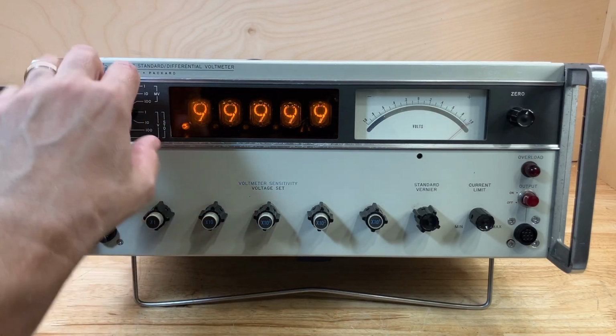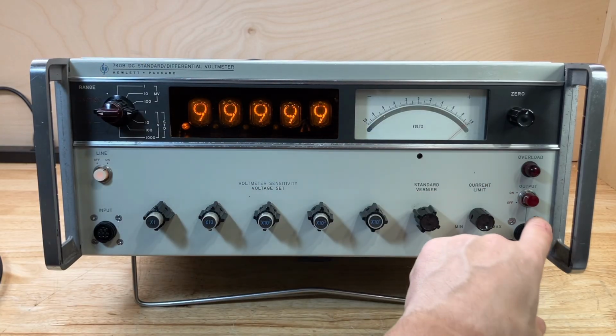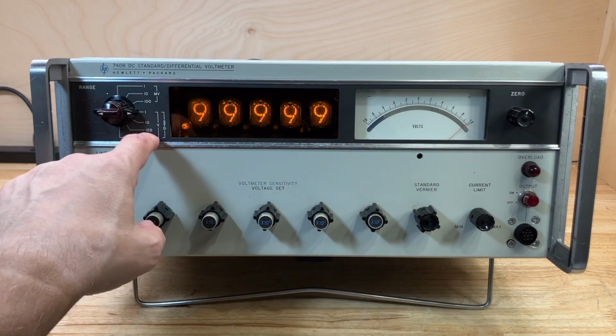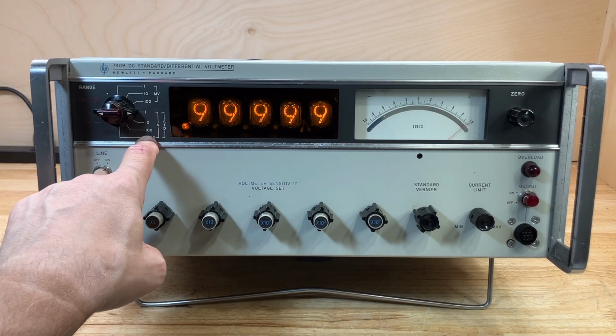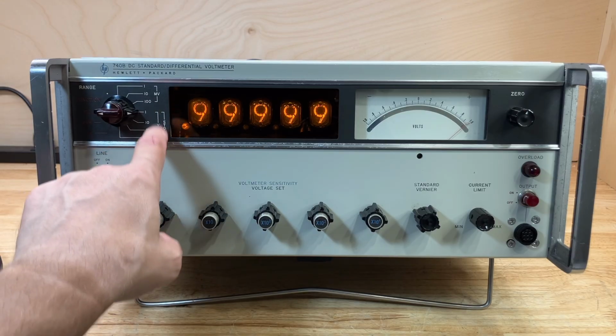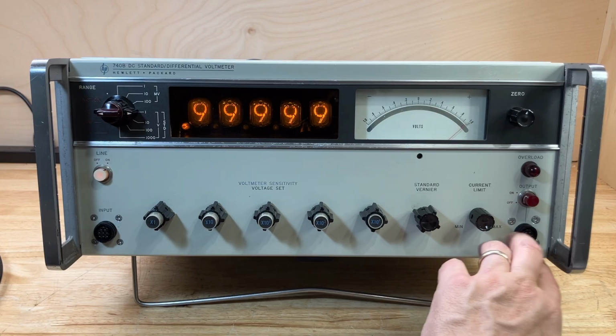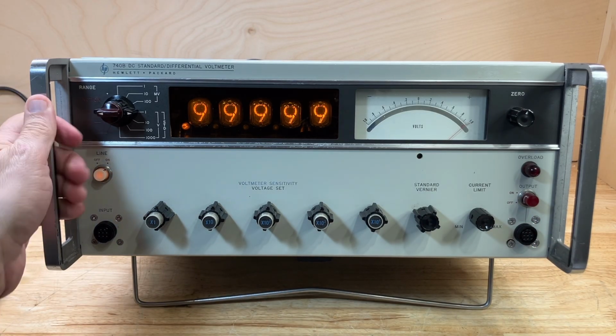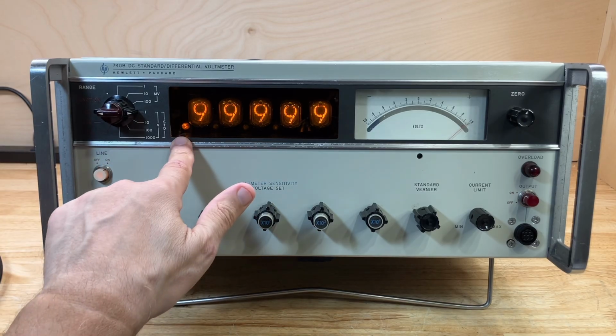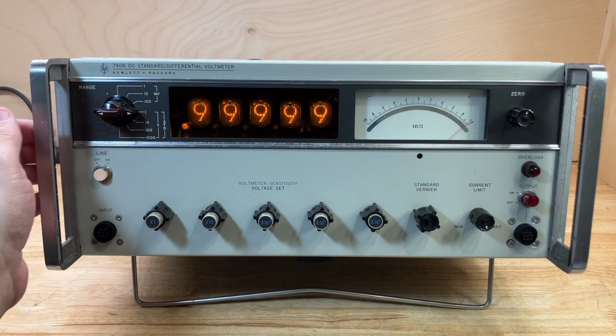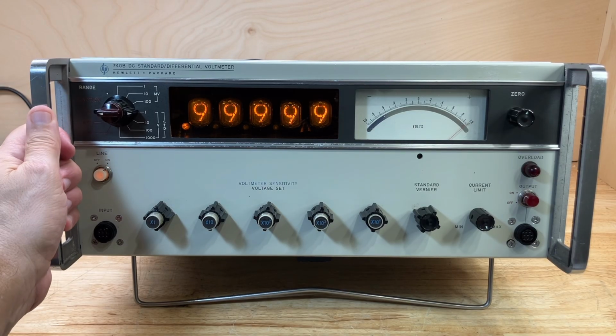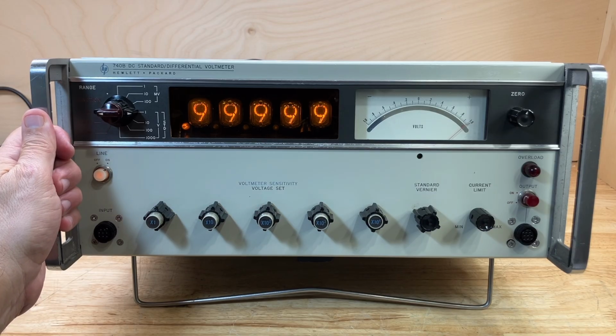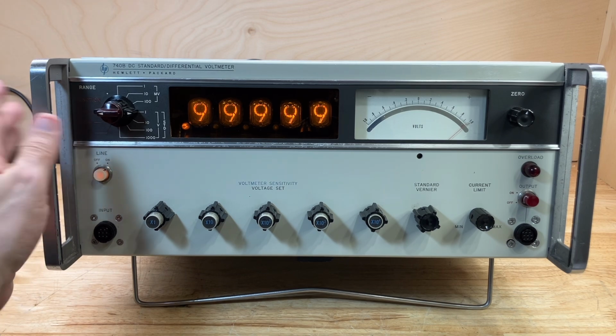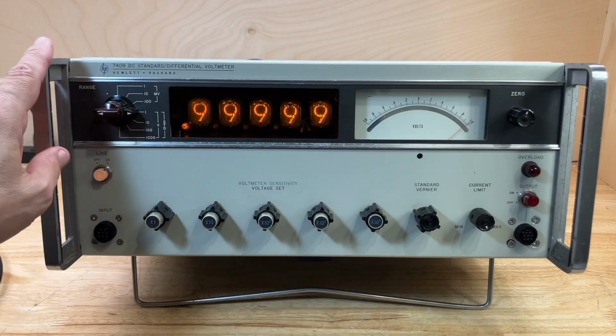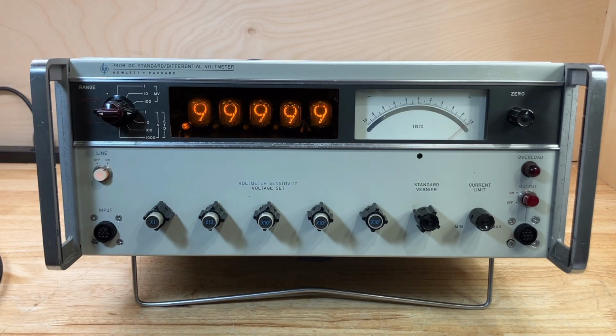The output of the DC standard is a precise 6-digit resolution DC voltage in ranges from 1 volt maximum to 1,000 volts maximum in times 10 steps. That voltage is available at the output over here and is used for calibrating DC voltmeters. I used one of these almost daily when I worked at Hewlett Packard in the 1980s to calibrate DC voltmeters of 3.5, 4.5, 5.5, and sometimes even 6.5 digits using this DC standard. Not this exact one, but this model number of DC standard. I used it in the 1980s for that purpose.